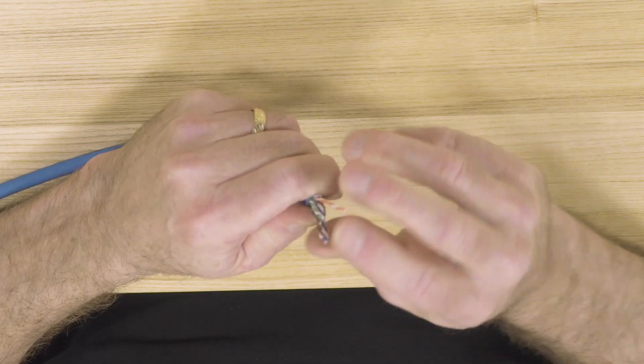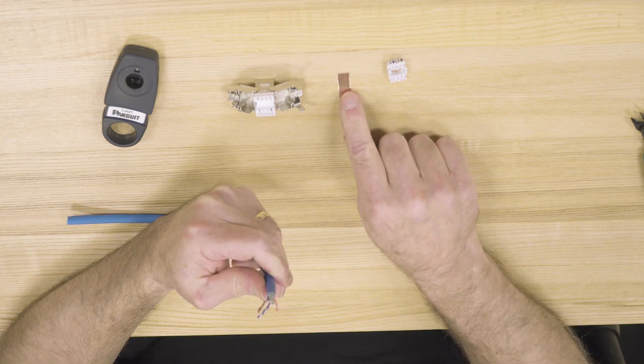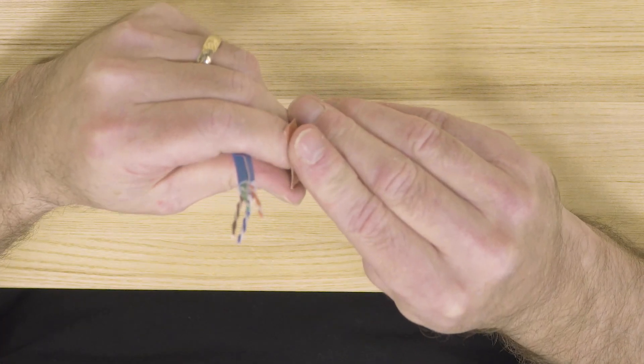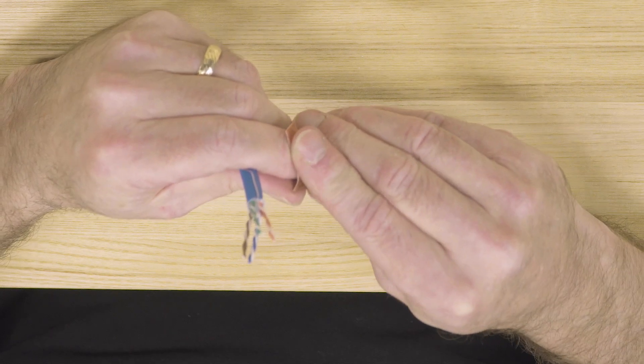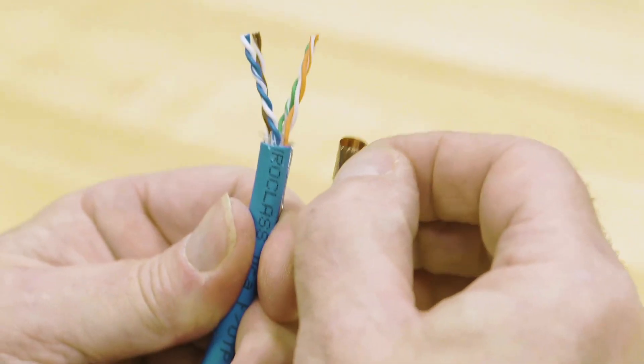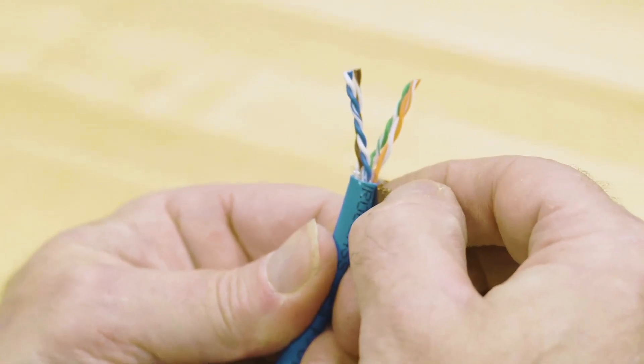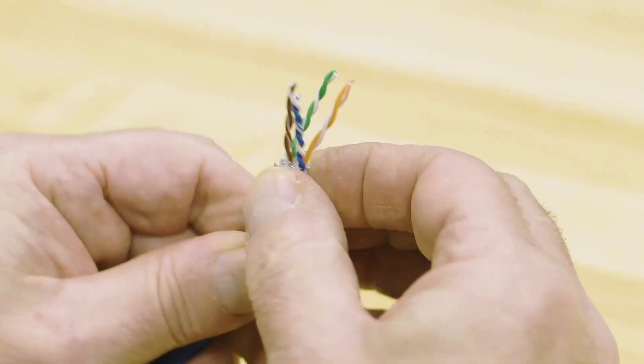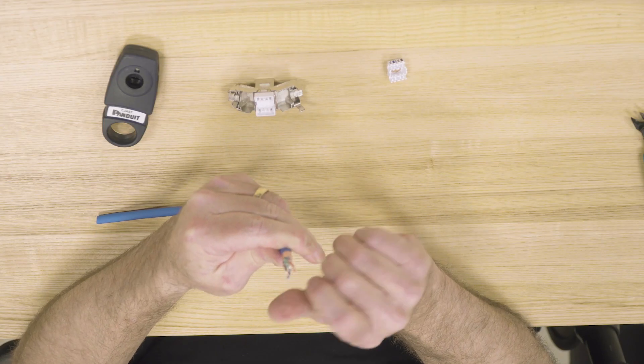Bring the conductors back up and take this copper strip that's been provided. Put that around the outer portion of the jacket, making sure to include and cover that drain wire. That'll cause a nice secure bond right there.